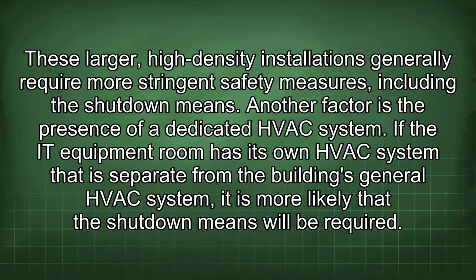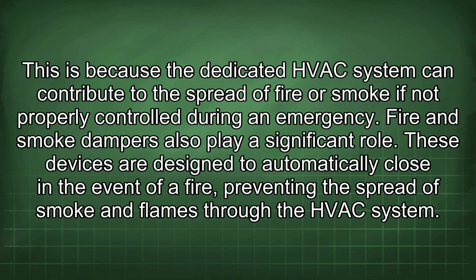Another factor is the presence of a dedicated HVAC system. If the IT equipment room has its own HVAC system that is separate from the building's general HVAC system, it is more likely that the shutdown means will be required. This is because the dedicated HVAC system can contribute to the spread of fire or smoke if not properly controlled during an emergency. Fire and smoke dampers also play a significant role.